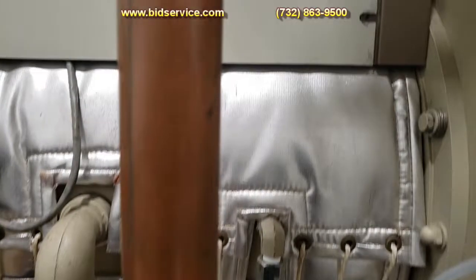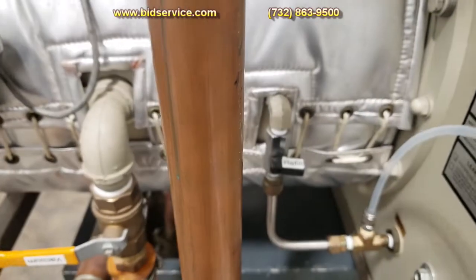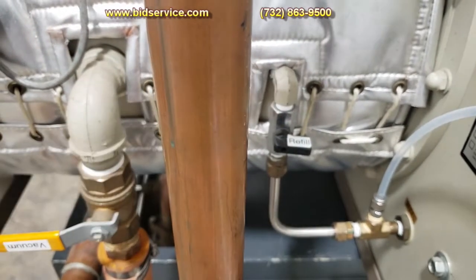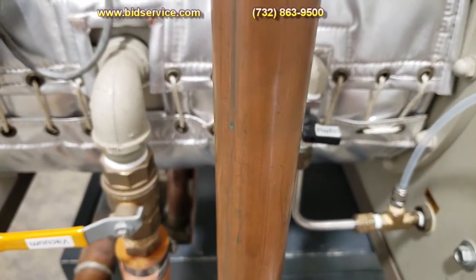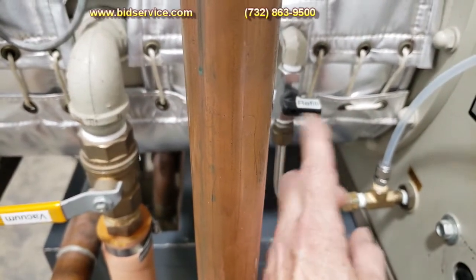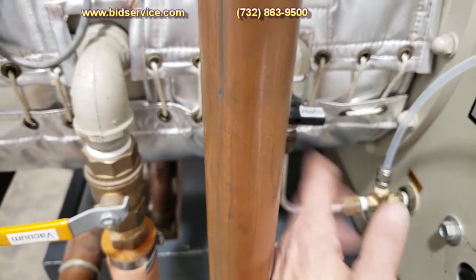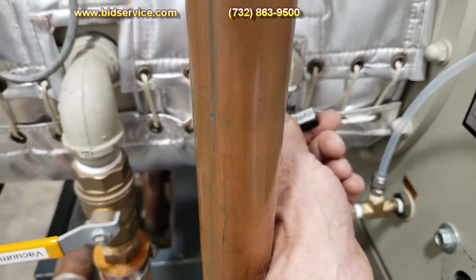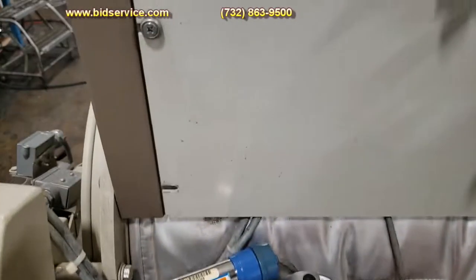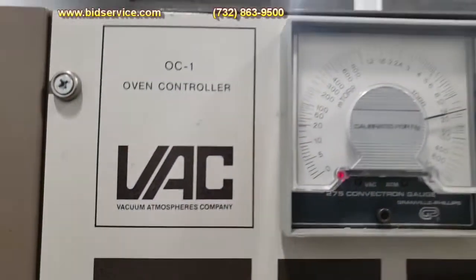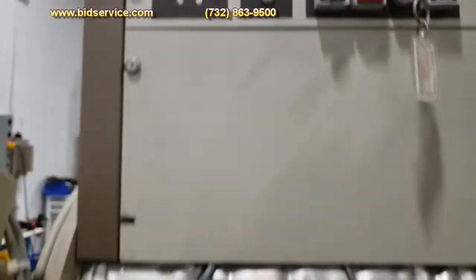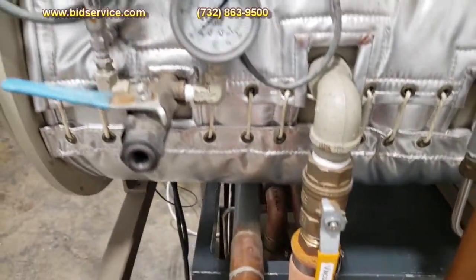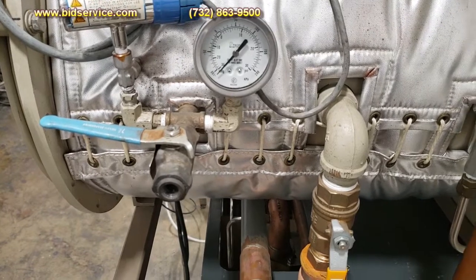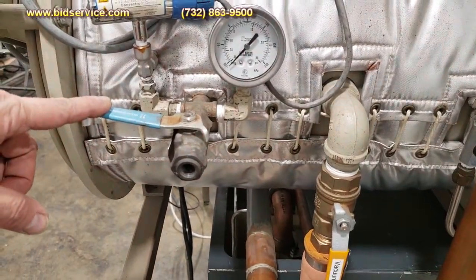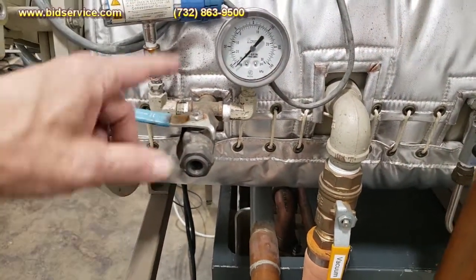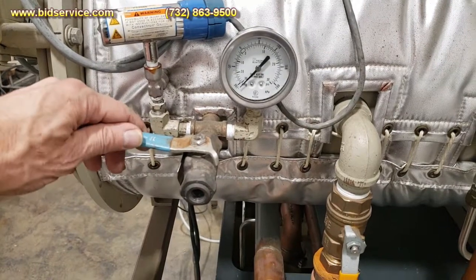To refill, there's a refill valve over here. Let's see if I can get that. There it is. This is inert gas coming from inside the glove box. So if you want to backfill with high purity nitrogen or whatever inert gas you're using, you can go ahead and open the refill valve. And just to show you that the vacuum level did change slightly. And then go ahead and open it up again to evacuate it. If you just want to open it up to atmosphere, you can go ahead and open this valve. This just draws in air from the outside into the antechamber. So we'll just leave that closed for now.